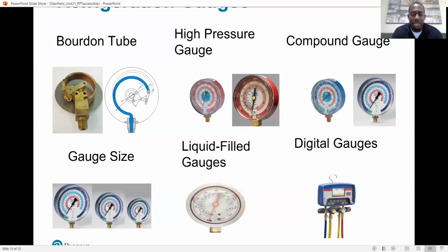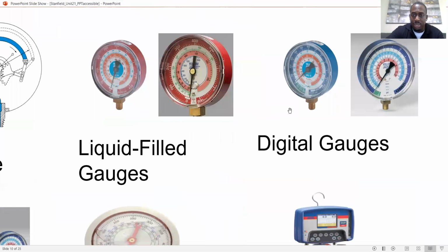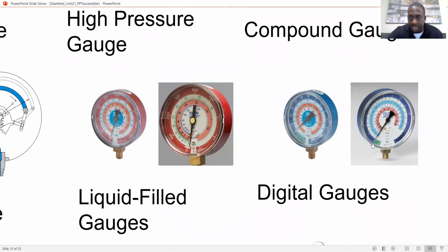So anyway, another thing I wanted to mention is the high side gauge, as they said, is just a pressure gauge, but the low pressure gauge is a compound gauge. It reads both positive and negative pressure. So notice zero, that's it, and that's all. The zero is as low as the high side gauge goes. But if you look at the low side gauge, which is a compound gauge, zero is here, but then you still have this green area below zero. That is a negative measurement. That's your vacuum that they're reading when you're doing an evacuation.